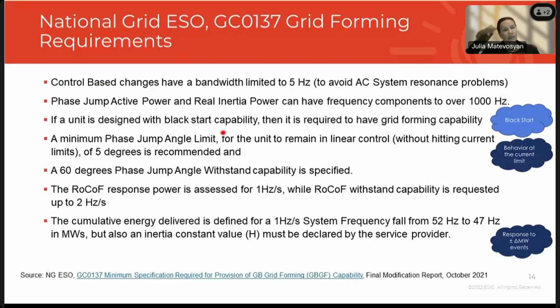And I also wanted to say that National Grid's requirements are slightly more detailed, but also most of the capabilities have to be announced by the inverter-based resource. So basically, they're not prescribed. You're supposed to have this much, I don't know, real inertia power, but you tell us how much real inertia power you have. And so there is a table that the inverter-based resource is supposed to fill in to announce how much capability they have for each of these functional specifications. And then the RoCoF power response is assessed for 1 hertz per second RoCoF, but there is also RoCoF withstand capability of 2 hertz per second. So that's basically ride-through for a RoCoF event. And then there is also more detail on the definition of what's defined as real inertia power. Go to the next one.